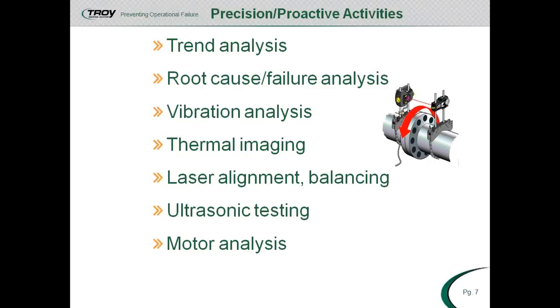Laser alignment and balancing supports our precision maintenance philosophy. Vibration analysis will find a misalignment, and vibration analysis will find balancing problems, but our advanced tools, the laser alignment tool and the balancing tool, will help those problems go away so we don't have a repeat offender. Ultrasonic testing utilizes the ability of an instrument to hear sound waves that are beyond the human ear. And a great example: any type of release like steam, air, water in a body rushing past an orifice, they give off ultrasonic sound waves.